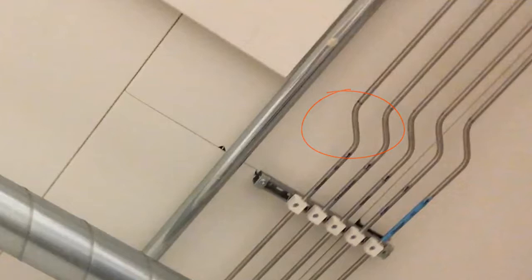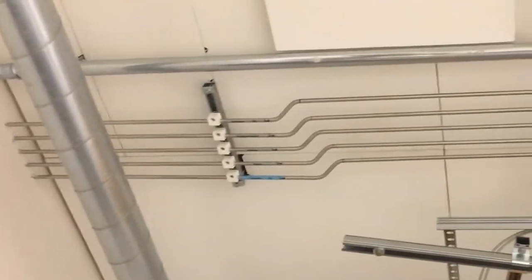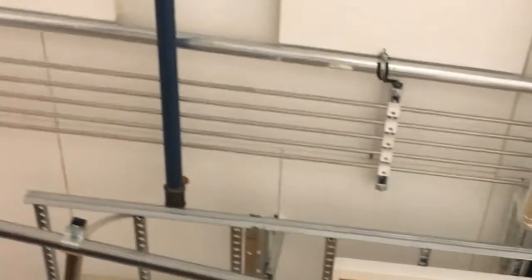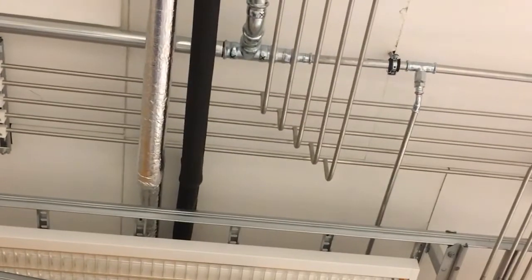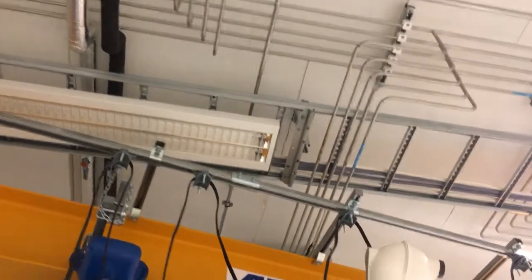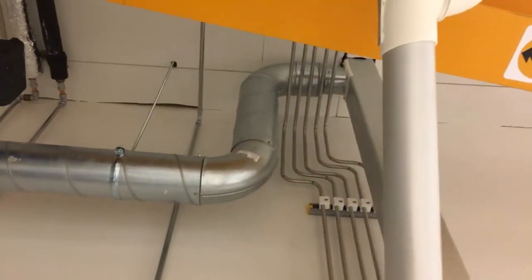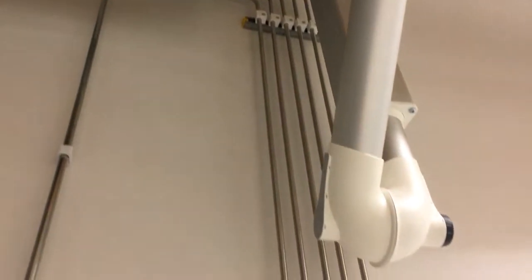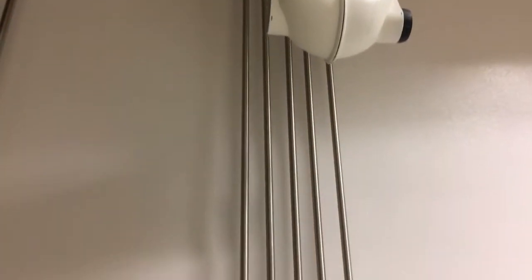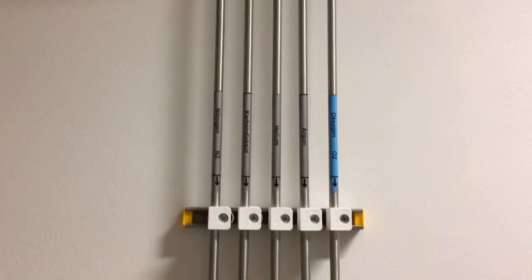Let's look at that further. It gets up, hugs the roof tightly so that it can get over this line. Here we have the pipe holders holding them here. And then here we have this other tube bonded to this, brazed or welded onto this, and we have a drop coming down so that we can get to a point where we use this. We follow this drop or perhaps the next drop over here. It's bent around with a whole bunch of fittings, getting around the ductwork and the ventilation air, following the wall down.